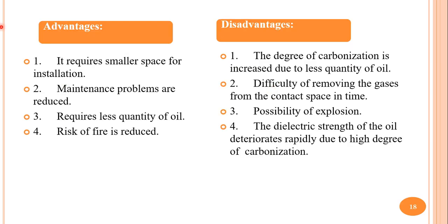The main advantages of the low oil circuit breaker are that it requires smaller space for installation, maintenance problems are reduced, it requires less quantity of oil, and the risk of fire is also reduced. The main disadvantages are that the degree of carbonization is increased due to the less quantity of oil, difficulty of removing gases from the contact space in time, and there is a possibility of explosion. The dielectric strength of the oil deteriorates rapidly due to high carbonization, requiring frequent oil replacement.